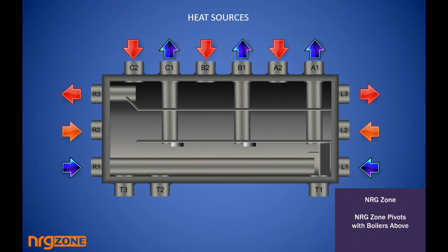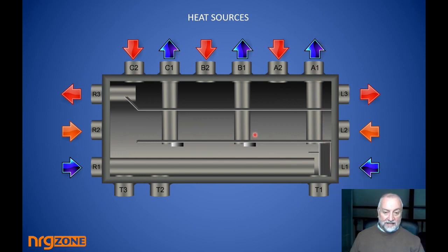We get the manifold, and let's say we put it on the wall, and we actually pivot it around the center point so that the zones are looking upwards. And now we're going to take our boiler, say for instance, in at the top. So if we're taking a boiler heat into C2, well, it's going to be in the top chamber. So if I take heat into B2, it's going to be in the top chamber, and A2 top chamber. Whereas if I'm drawing heat back to boilers that are fitted directly above the manifold, my return would be now using the bottom chamber in this scenario.